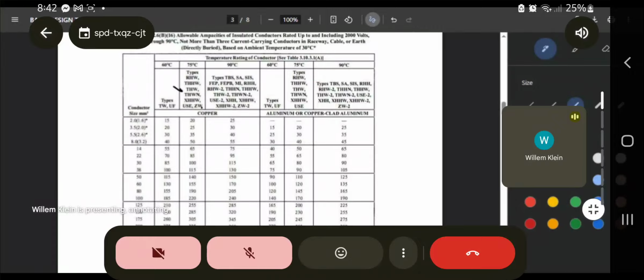Okay. I think they did not use copper for that one. They used aluminum THW because it was mentioned 83 amperes, so they used 38 millimeter square size. So for the copper, if they used copper, it should be smaller, around 22 only or 30. Okay? So these two are close to the 83 amperes computed. But for the aluminum, the next higher to the 83 is your 90 amperes here. Okay? So that is 38 millimeter squared for the aluminum THW.